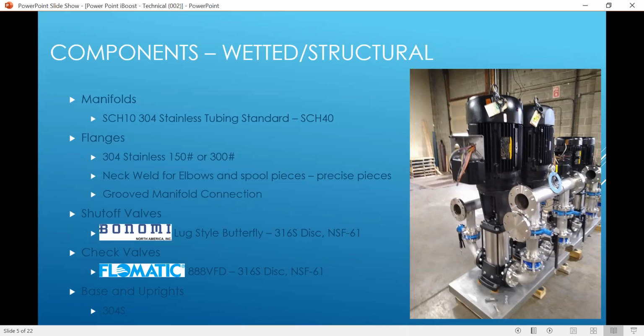Those are your wafer checks. We do not really use a threaded check valve very often. We like the fact that our check valves are the lug style, and they're just a little bit easier to work on. They're a little bit easier to service if you have to do a change on the unit than having a threaded connection.